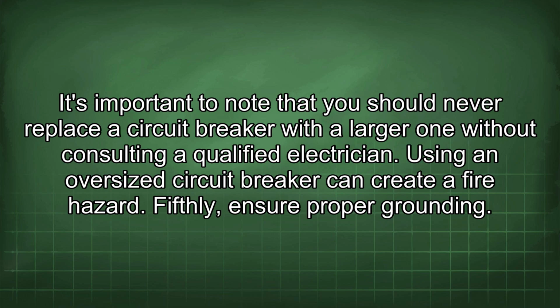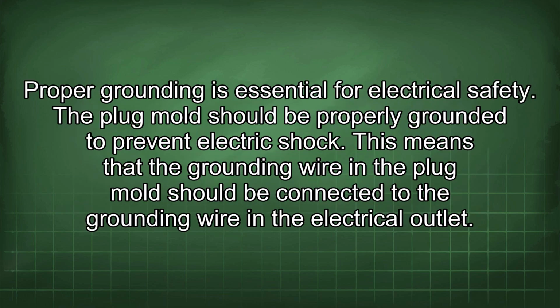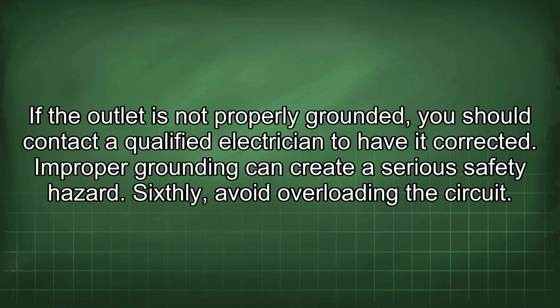Fifthly, ensure proper grounding. Proper grounding is essential for electrical safety. The plug mold should be properly grounded to prevent electric shock. This means that the grounding wire in the plug mold should be connected to the grounding wire in the electrical outlet. If the outlet is not properly grounded, you should contact a qualified electrician to have it corrected. Improper grounding can create a serious safety hazard.